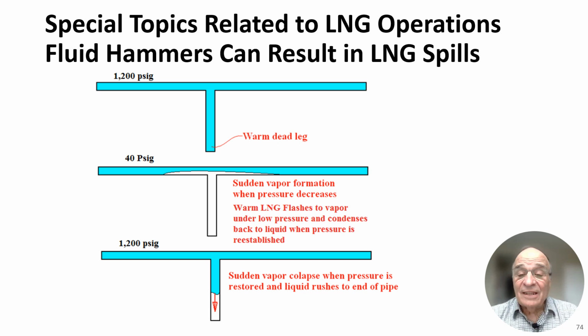When it hits the dead end, boom, there's a water hammer. That water hammer can be a spike in pressure that can cause this pipe to rupture, or can cause a valve at the end of this pipe or any other equipment to rupture and cause a large leak. So this is something to be concerned about when you're dealing with systems that have been pressurized and then depressurized and then repressurized. So how would you repressurize this to 1200 psi?